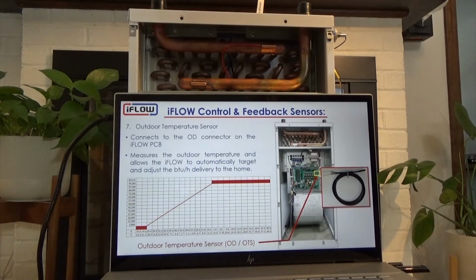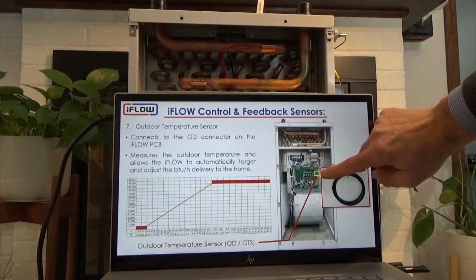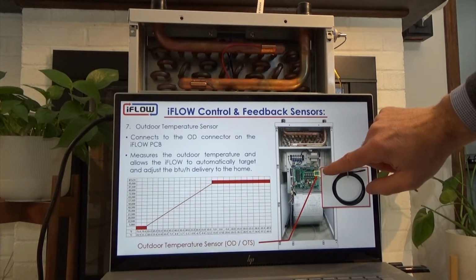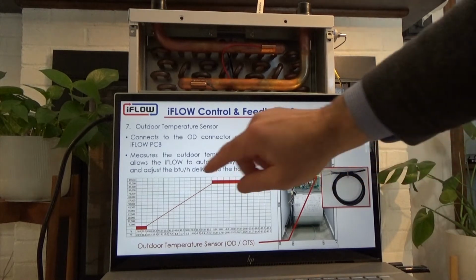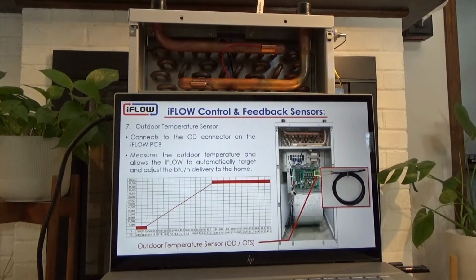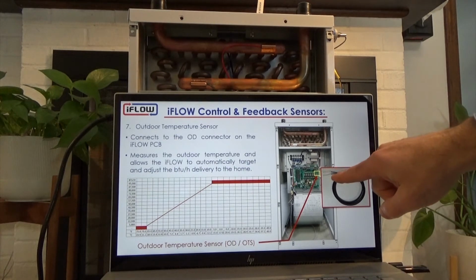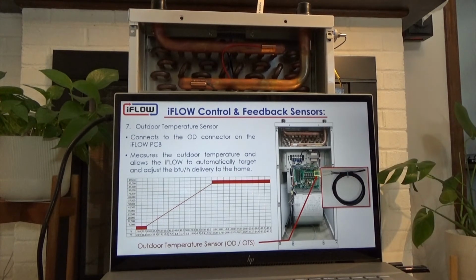The next sensor is our outdoor temperature sensor. The outdoor temperature sensor connects to the board at the upper right corner, and I will show you that contact. What the outdoor temperature sensor does is measure, of course, the outdoor temperature, and then feed that back to the unit. With that temperature, the unit can then decide at what BTU level it needs to deliver into the home.